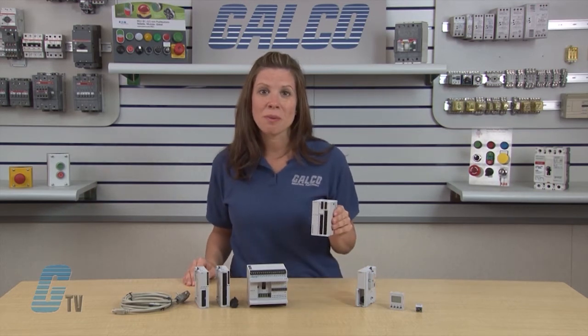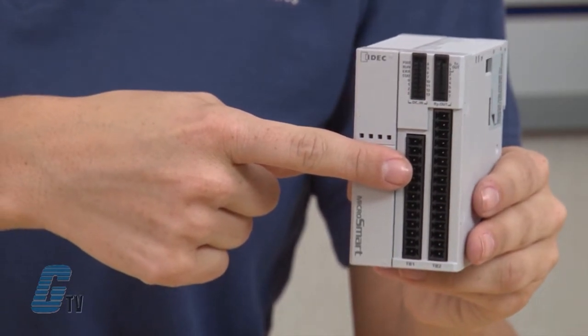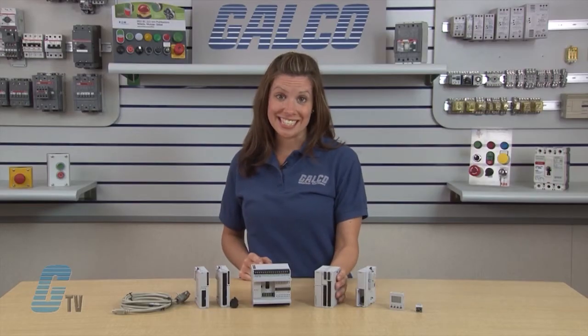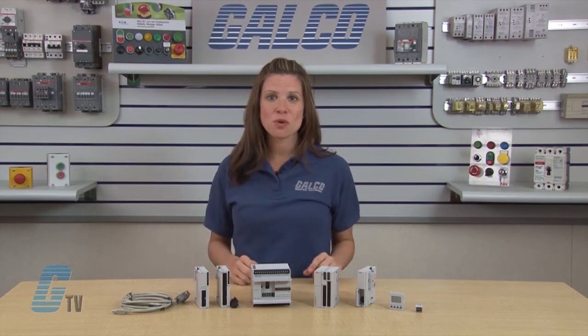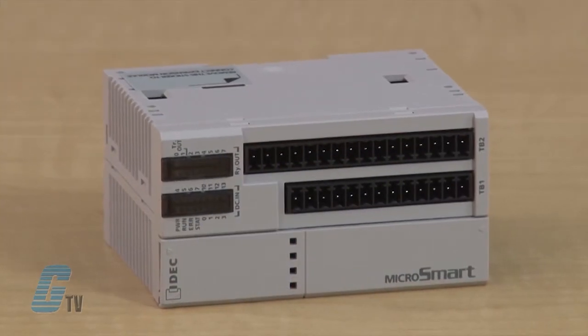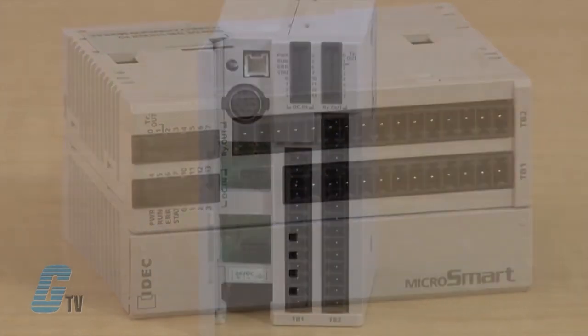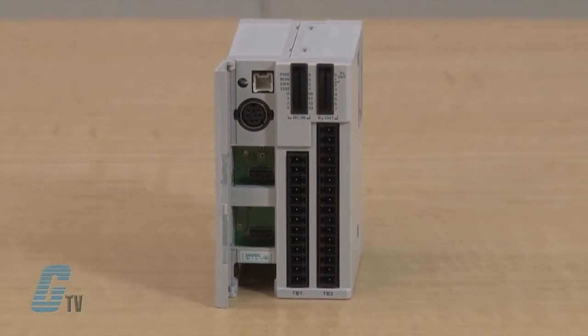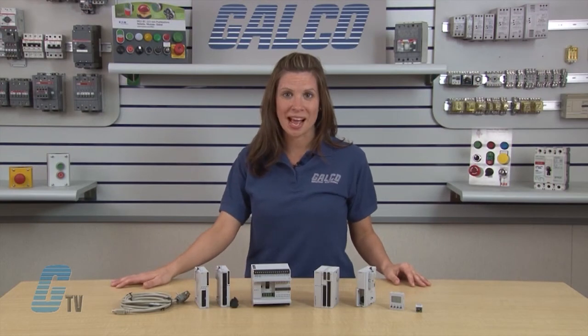The SlimType CPU module has 20 or 40 input-output terminals and operates on 24 volts DC. The total input-output points can be expanded to a maximum of 264. SlimType CPU modules have a program capacity of 27,000 bytes or 31,200 bytes, which is approximately 4,500 or 5,200 steps.